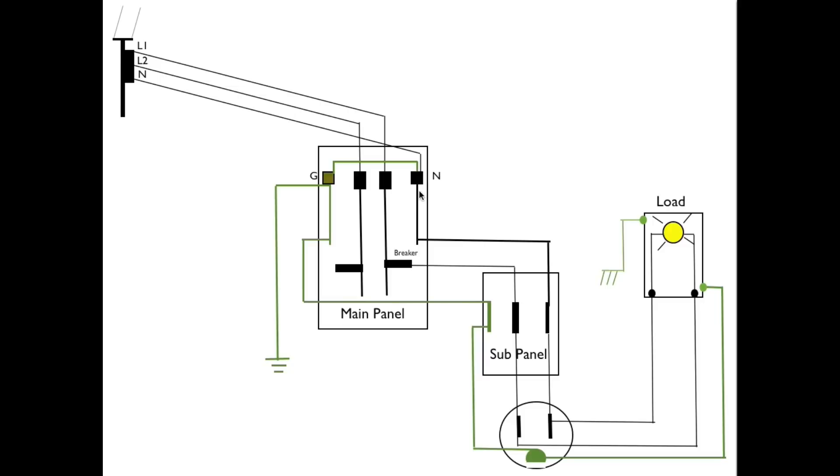They are separate and this is the way it's supposed to be. This is how it's supposed to be designed. So I have one side of power coming in here going through say another breaker and a sub panel. I put the sub panel in there just to illustrate the difference a sub panel is from a main panel. The sub panel cannot have the ground and the neutral connected together.